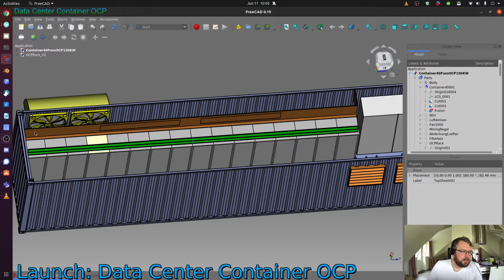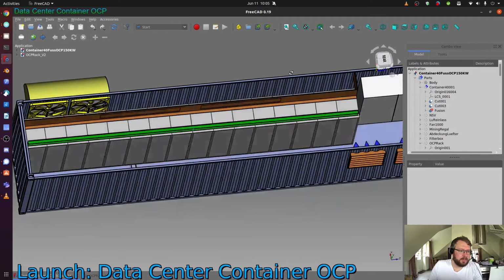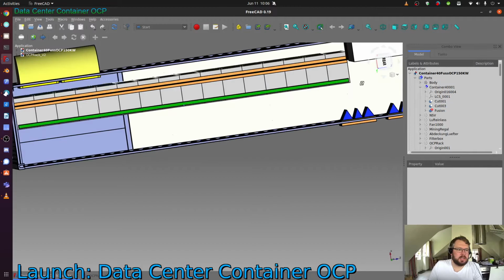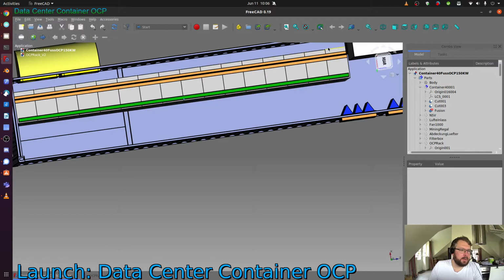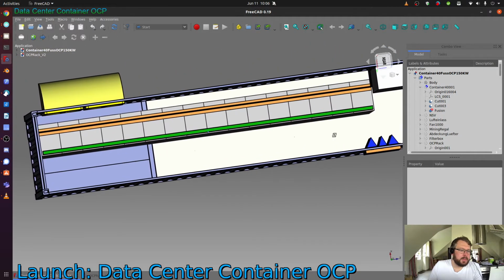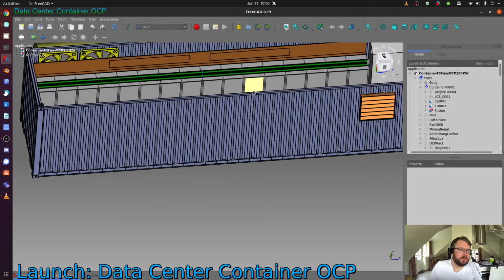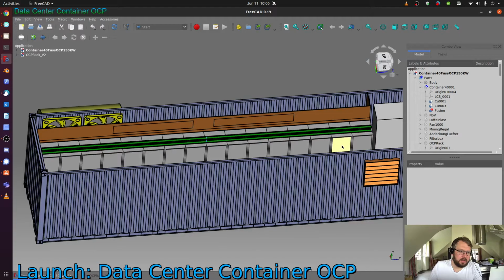This brown part is an easy separator for the hot and cold aisle. If you look at this, you have a separation — this is the part where you access the servers. For OCP you can do all the handling from the front, and you have limited space in the back, which is only used to move out the hot air. To ensure that hot air doesn't move backwards in front of the server, we have a hot and cold air separator with large flaps that, in low temperatures or when you need to raise humidity, actually open and feed air back to the front.